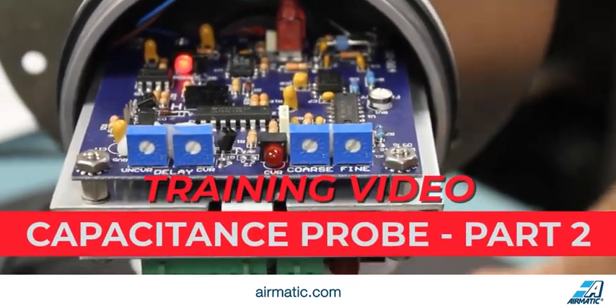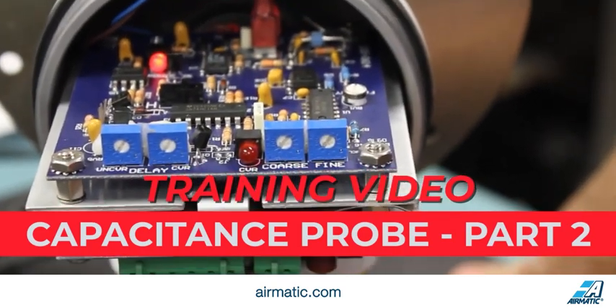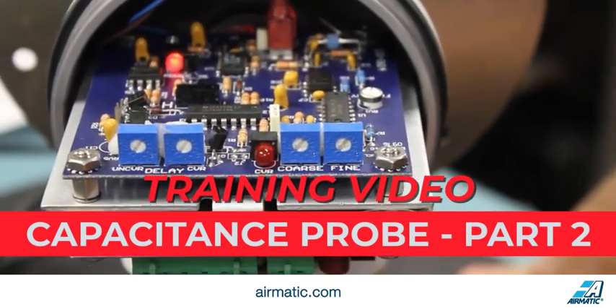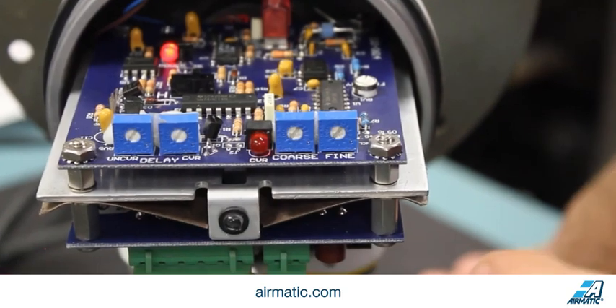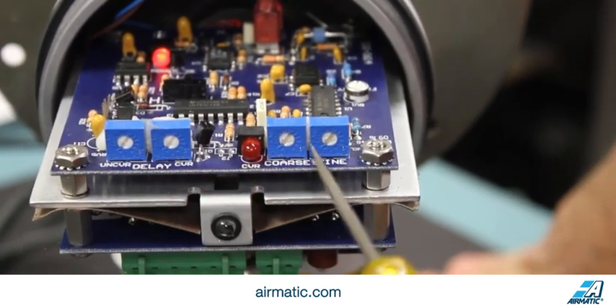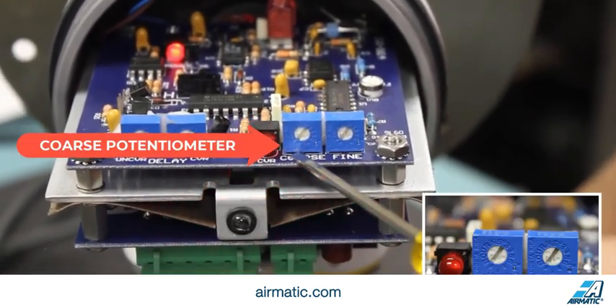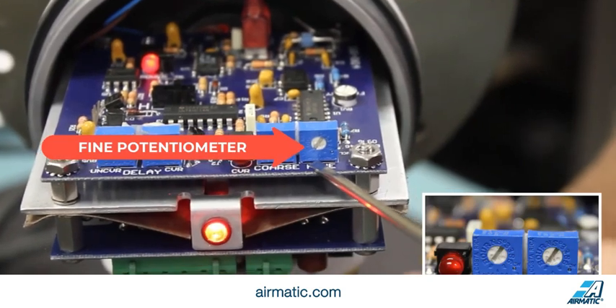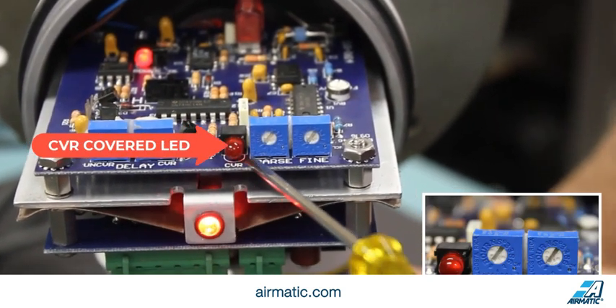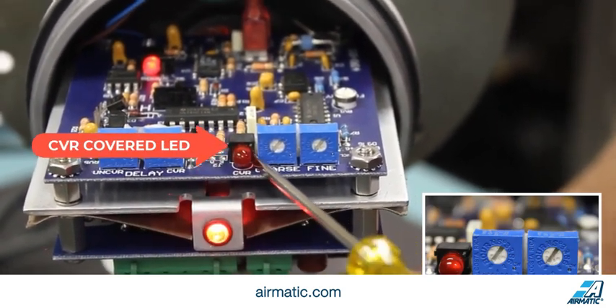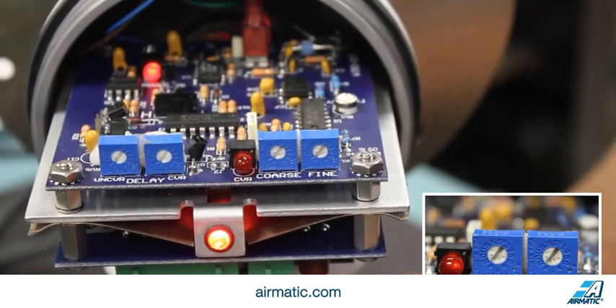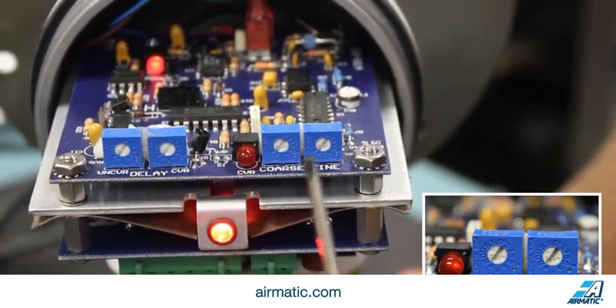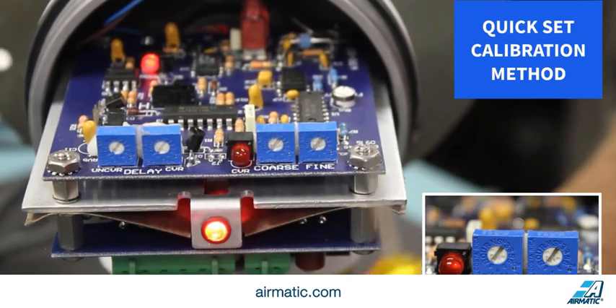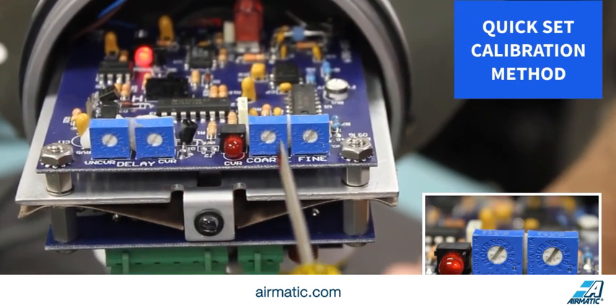Okay, now we're going to go through the calibration procedures for our ProCap capacitance probes. To calibrate the probe, we're going to deal with two potentiometers, a coarse potentiometer and a fine potentiometer, and then we're going to look at the covered LED, the CVR LED, which is right beside the coarse potentiometer. So this is going to be our quick set calibration method.